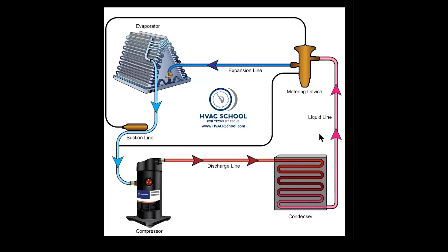It's very rare to see restrictions in the other three lines. The expansion line is rarely even a line except on ductless systems. The suction line very rarely has a restriction unless it has a suction line dryer. The discharge line almost never has a restriction, although I have seen it when somebody brazes in a compressor and leaves a bunch of boogers in there, restricting the flow — that can definitely cause high head pressure.